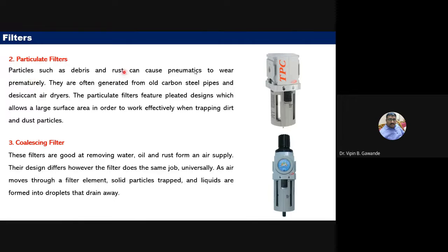The second type is the particulate filter. Particles inside the pneumatic system cause wear and tear. They are often generated from old carbon steel pipes and desiccant air dryers. Particulate filters provide a large surface area to efficiently trap dirt and dust particles, preventing wear and tear of the system.